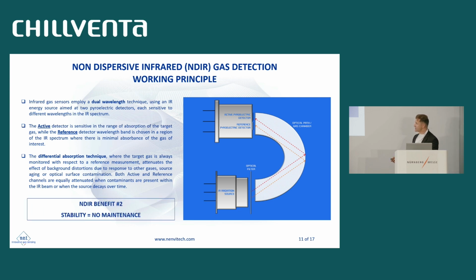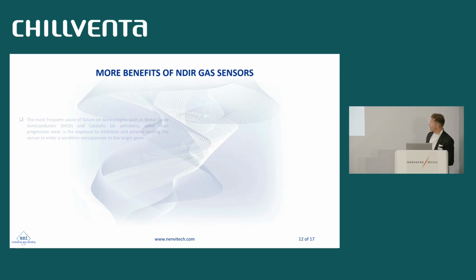That means that NDIR sensors have greater stability than other technologies on the market, which over time tend to wear down. And from that property derives the need for no maintenance. The sensor will maintain its calibration over time without periodic recalibration or frequent maintenance.